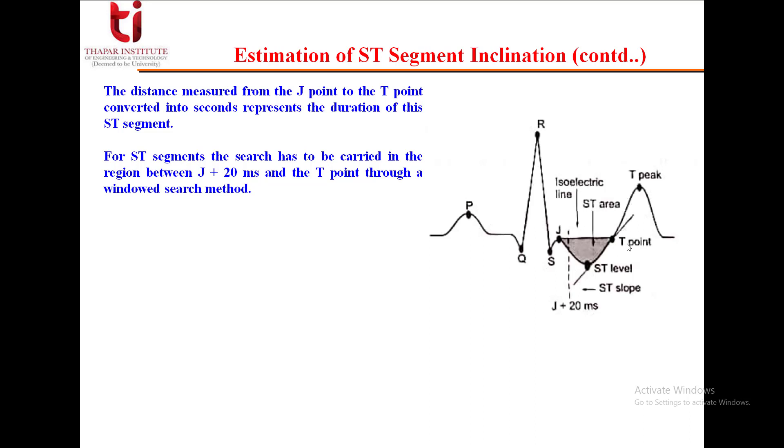The distance measured from the J point to the T point, converted into seconds, represents the duration of the ST segment. For ST segments, the search has to be carried in the region between J plus 20 ms and the T point through a windowed search method. The point of maximal depression or elevation in the window is then identified. The ST segment levels are expressed as the absolute change with respect to the isoelectric line.